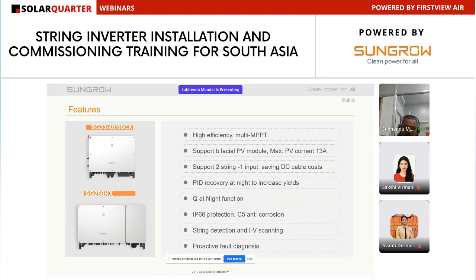Whatever PID is affected in the daytime, to recover that PID we have the PID recovery function at night time. So we have the Q at night function, which is called reactive power to grid at night. We can feed the reactive power from the inverter, and for this case we don't require any external capacitor bank or external things. Our inverter is IP66 protected, so we can install it outside also, and it has C5 anti corrosion. Our inverter also has string detection and an IV scanning system, which is optional, and it has a proactive fault diagnostic system.